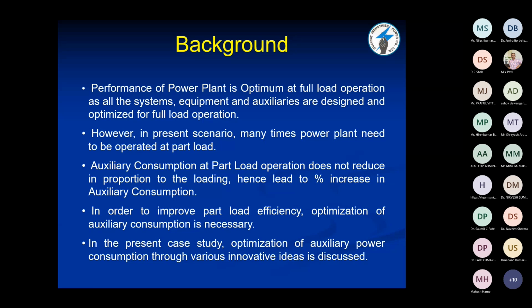Any gas turbine or steam turbine comes with a basic design, so we cannot change the basic design. The performance of a power plant is optimum at full load operation, as all the systems, equipment and auxiliaries are designed and optimized for full load operation. Okay, but now, looking at the price of gas and the present scenario, the plant is not operating at full load. Hence, in the present scenario, many times the power plant needs to be operated at part load, because there is excess power, and basically Gujarat is power surplus. So many times, as per the grid requirement, we have to operate our plant at part load.